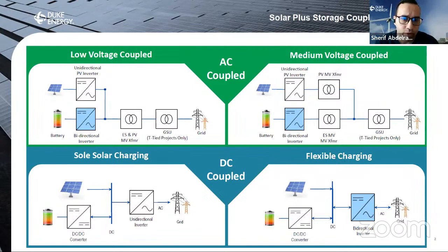In regard to the architectures available for solar plus storage systems, they can mainly be categorized into 2 buckets: one AC coupled, and the other DC coupled. For AC coupled systems, as the name implies, the battery system is tied to the solar system on the AC side. And depending on where that tying occurs, it could either be medium voltage coupled or low voltage coupled.